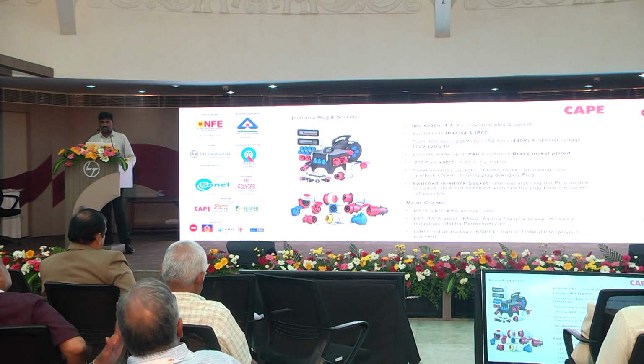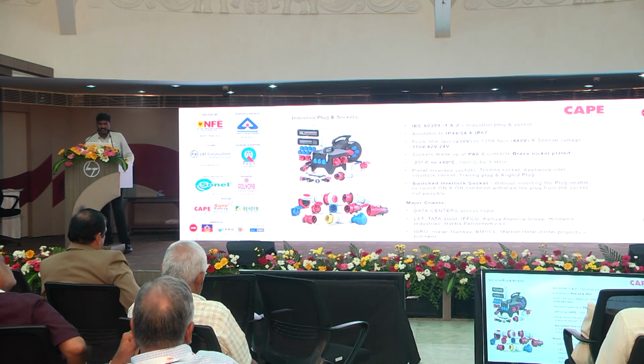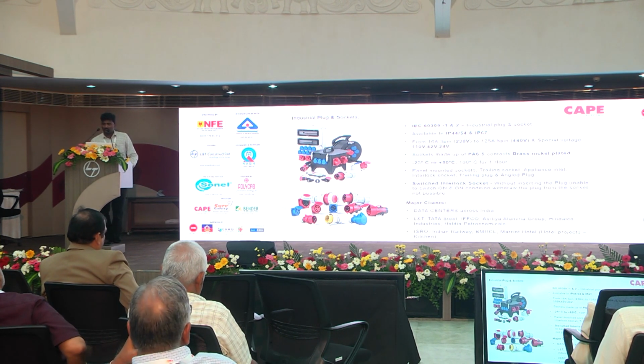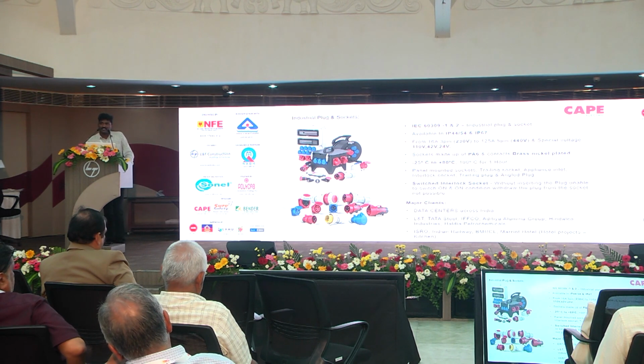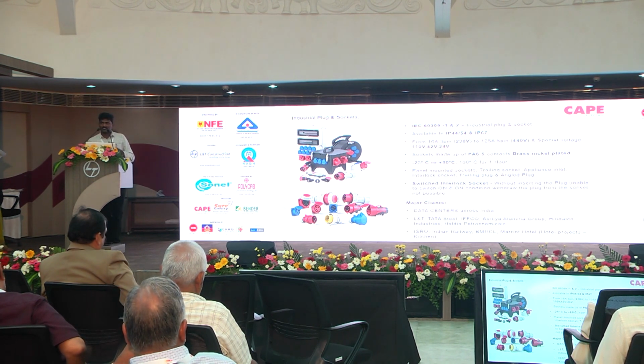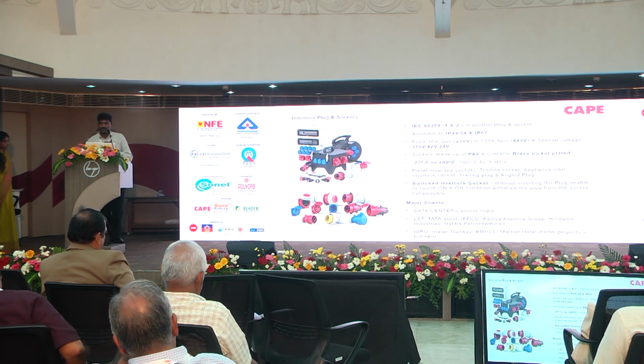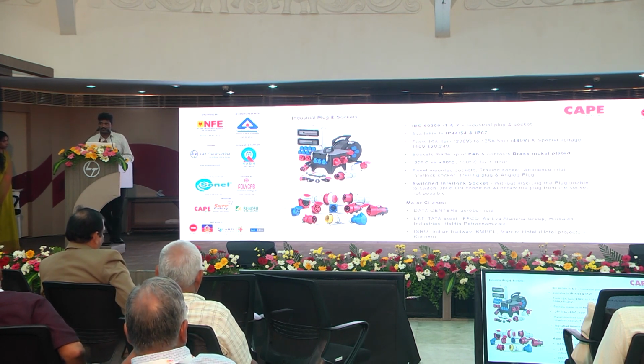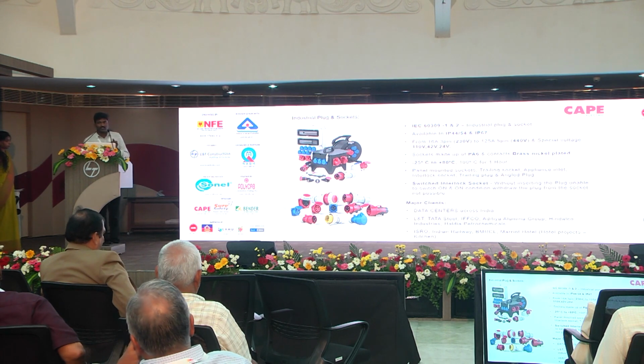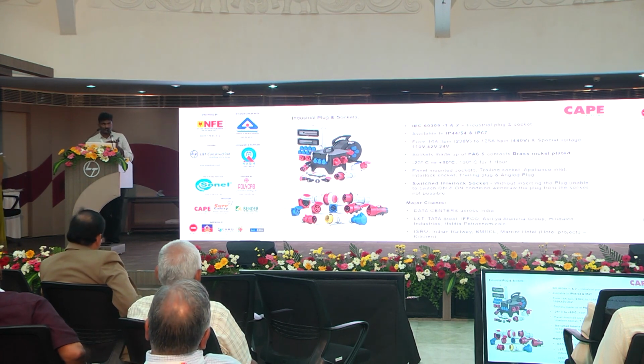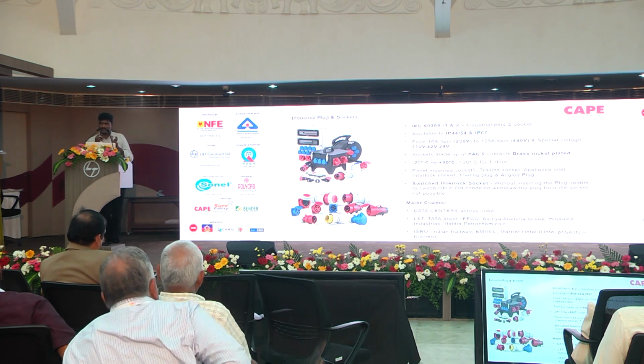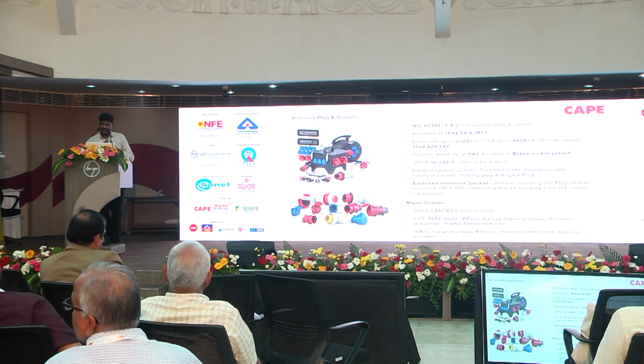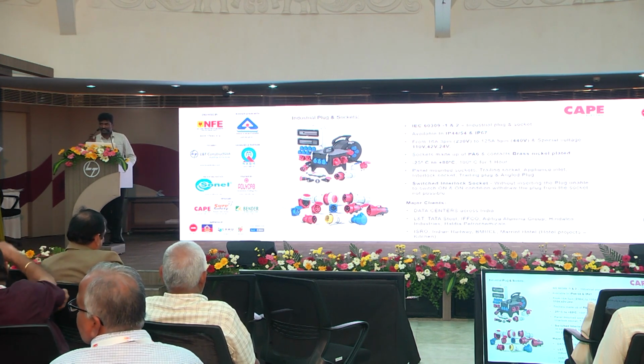We have socket ranges like panel mounted sockets and panel mounted inlets, trailing sockets, trailing plugs, interlock sockets, phase inverters, and switched interlock sockets, mostly used in data center networks. A switched interlock socket means the switch cannot be turned on without inserting the plug, so no supply is drawn out from the socket. Once the switch is on, we cannot withdraw the plug. So there is additional safety, because at most sites without interlocking, people simply open the top cover of the socket and insert the wire without the plug, which can cause accidents and short circuits. To avoid these, it is much safer.